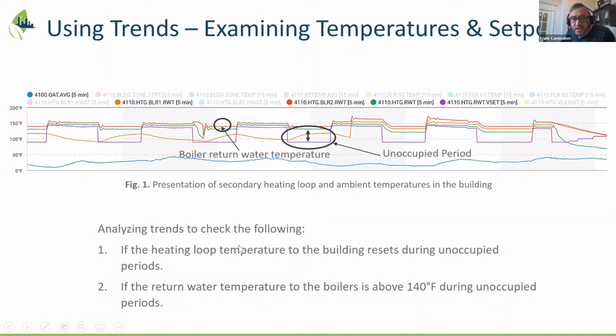If you're looking at the heating loop temperature, we want to make sure that it resets during unoccupied periods. The whole point is that during unoccupied periods, we want the building to use less energy, right? So there's no need to heat it as much. We reduce the unoccupied temperature setback, so we're looking to see whether it is actually doing that. And we want to make sure the return water temperature to the boilers is in an operable region so it doesn't damage the boiler. We can't stress this enough: energy efficiency should never compromise the integrity of the equipment. So we ensure that the return water temperature is above 140.